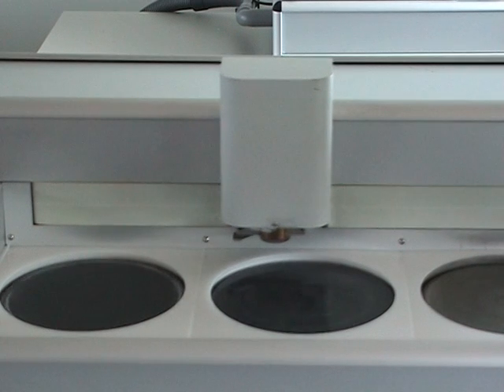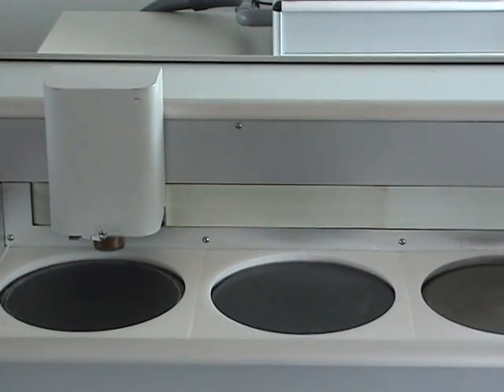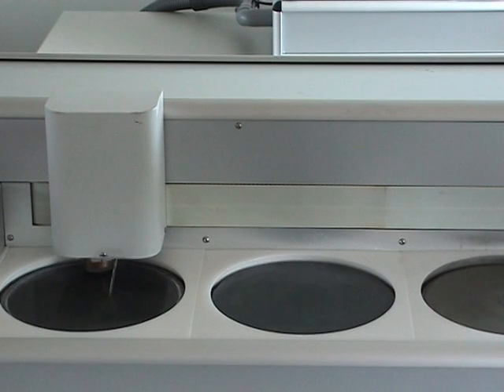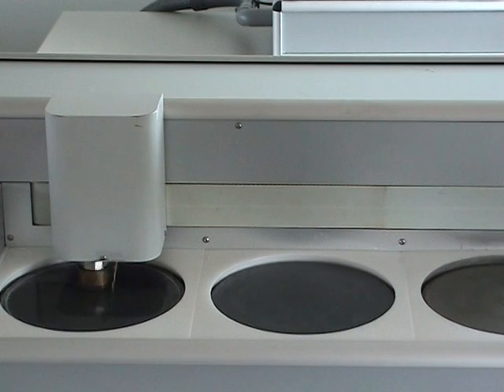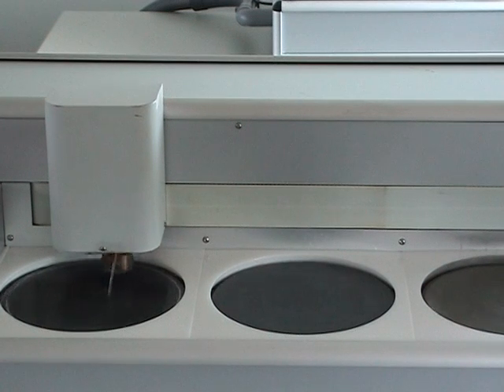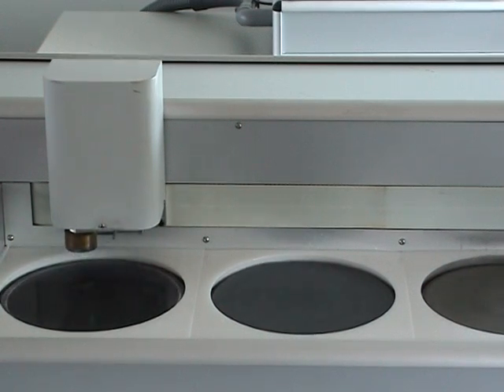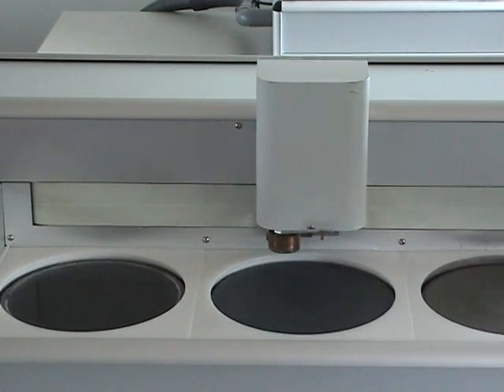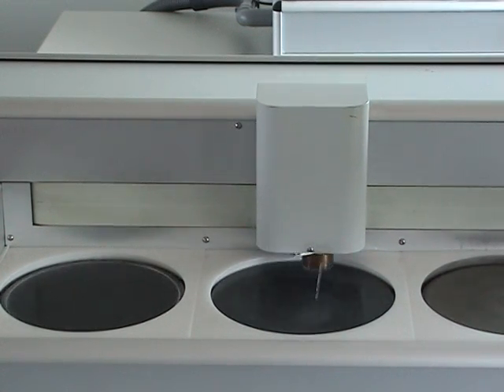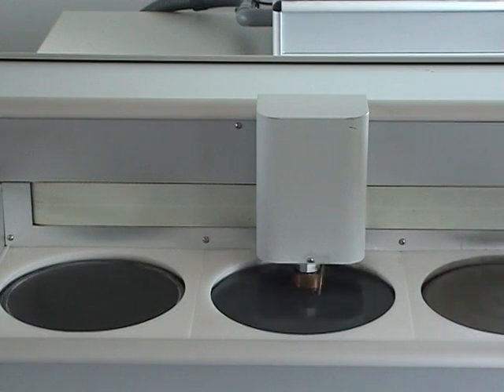After the reference measurement, the rough grinding is done on the left station. The SPA machine is fully programmable, so you can program rough and fine grinding individually. The whole amount of grinding, rough and fine, is exactly the number which was programmed as offset in the TSM sawing process. After completing rough grinding, the machine will continue automatically with fine grinding.